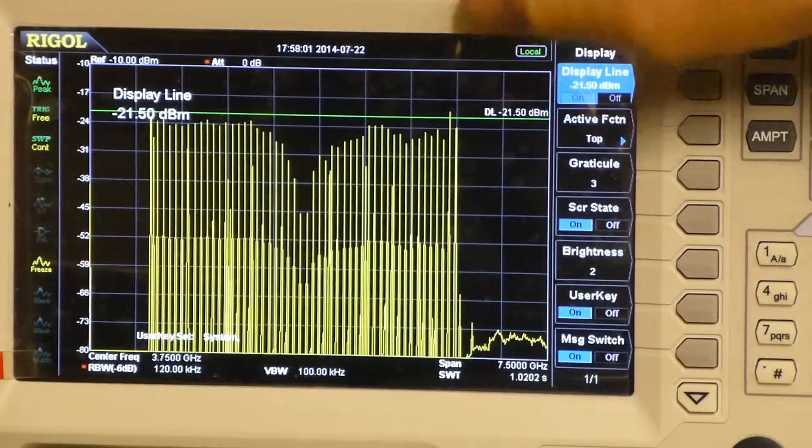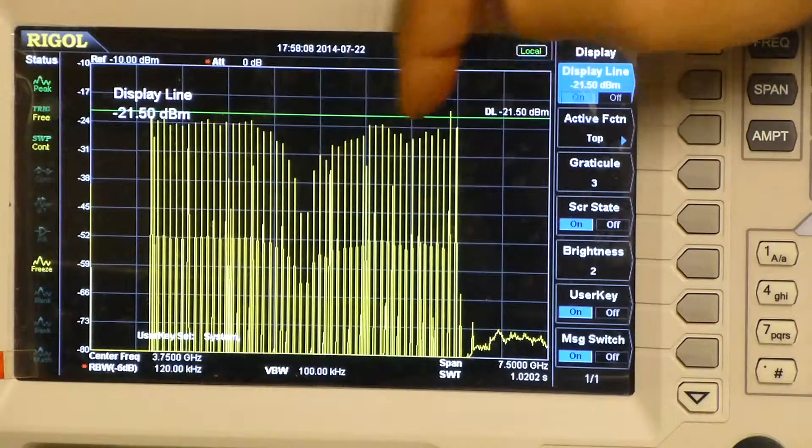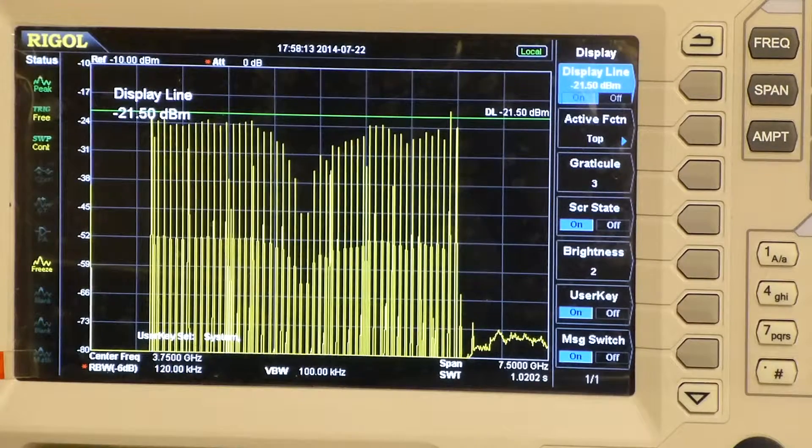More usefully, where you have a standard for EMC to meet, you will normally see a pass-fail line across the screen showing the spectrum profile that you have to meet for your emissions.